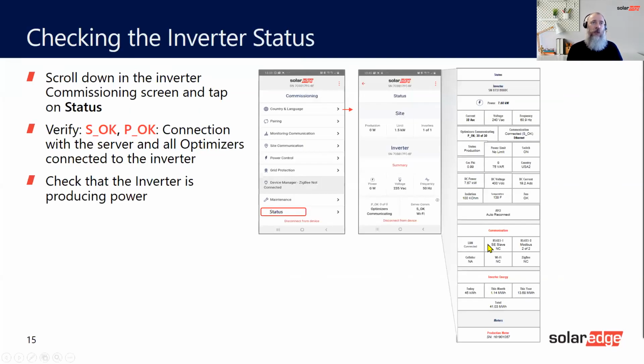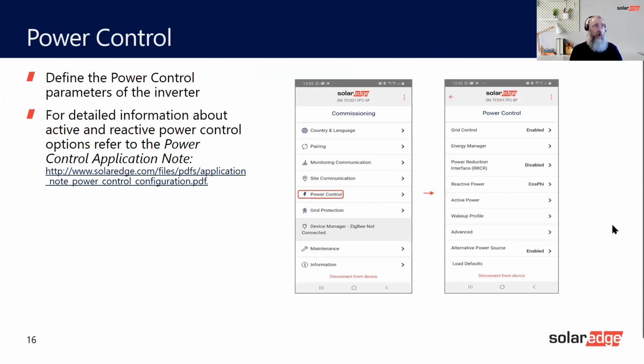You can see on here the Modbus RS485-2 and RS485-1, for the old terminology of slave, which is now leader and follower. So each inverter has two RS485 connections, unlike the LCD screen. So we have two buses, one for connecting inverters together and firefighter gateways and consumer control gateways, and the second one for the meters. You can have either or, it doesn't matter which one you use. We do have more specific power controls, again in the main commissioning, where you've got reactive power, active power, and advanced settings, and you can change this to suit your region should you need to.